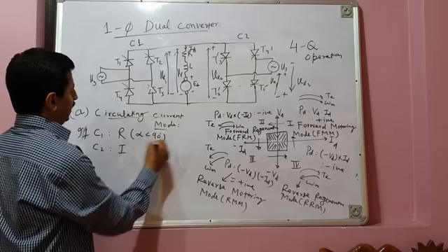So in a nutshell, to go from forward motoring mode to reverse motoring mode, your machine has to go through forward regeneration mode, where it is stopped. And similarly, to go from reverse motoring mode to forward motoring mode, the machine has to go through reverse regeneration mode, where it will be stopped. The advantage in forward or reverse regeneration mode is that the machine is stopped and braking energy is not wasted. It is fed back to the source, because this is an electrical way of braking the machine. You are not using any mechanical brake.